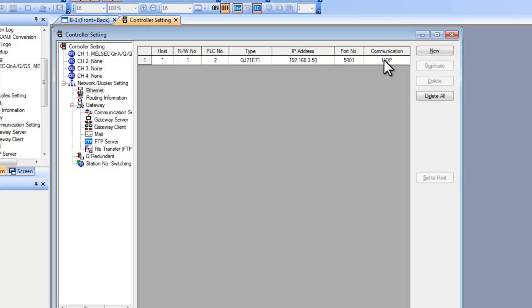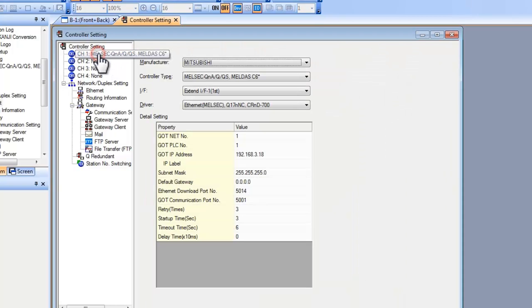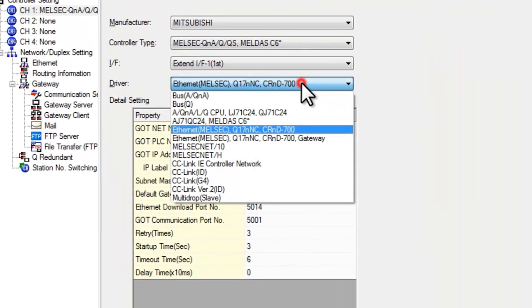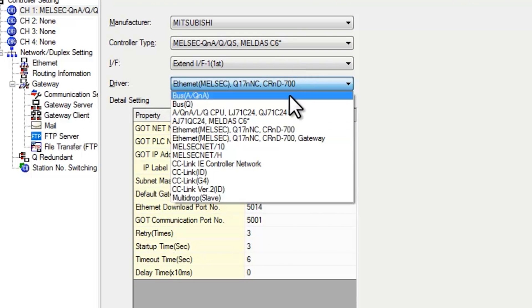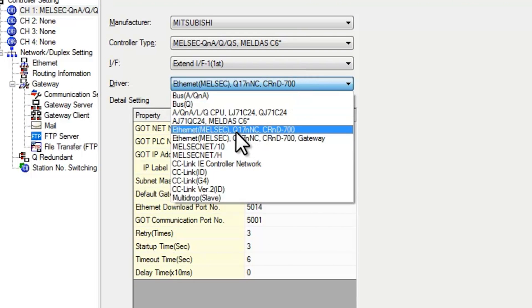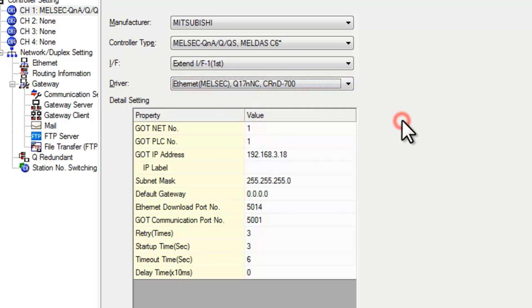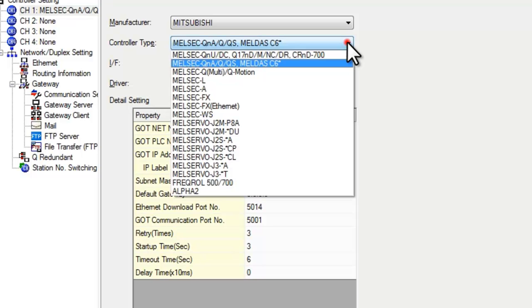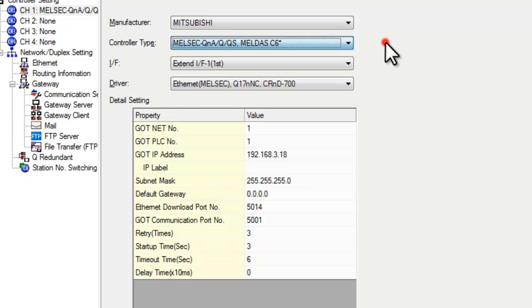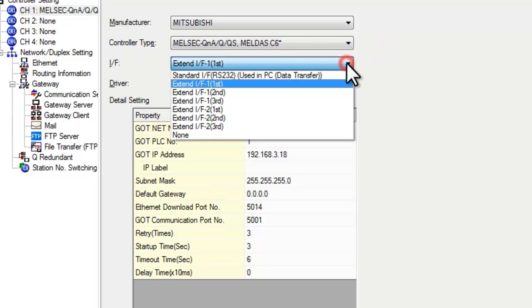And the port number leave this alone as well as the communication protocol setting. In the channel setting for the GOT you need to make sure that your driver has been selected correctly. Make sure that you select for Ethernet on a queue. Make sure you select this option here. And your controller type. Make sure that you have that selected as well in accordance with the controller that you have connected.